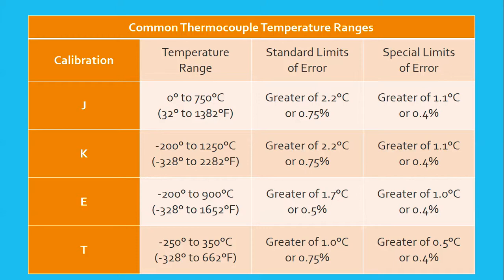Type E minus 200 degrees to 900 degrees Celsius, greater of 1.7 degrees Celsius or 0.5 percent as standard limits of error. Special limits of error: greater of 1.0 degrees Celsius or 0.4 percent. Type T temperature range minus 250 degrees Celsius to 350 degrees Celsius. Standard limits of error: greater of 1.0 degrees Celsius or 0.75 percent. Special limits of error: greater of 0.5 degrees Celsius or 0.4 percent.